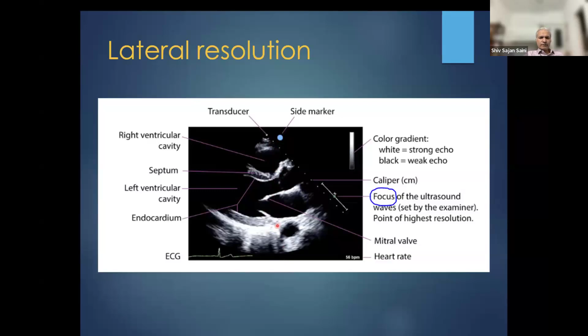You improve your lateral resolution. The next is the temporal resolution. Temporal resolution, we have discussed, is the ability of the machine to identify that a particular object has moved from one place to another. So it is synonymous with the frame rate. So what is frame rate? The machine takes some time to scan one frame. There is one beam, it goes and scans the entire frame. The time it takes to scan an entire frame is one frame, and the rate is 1 divided by the time the machine takes to scan the entire frame.